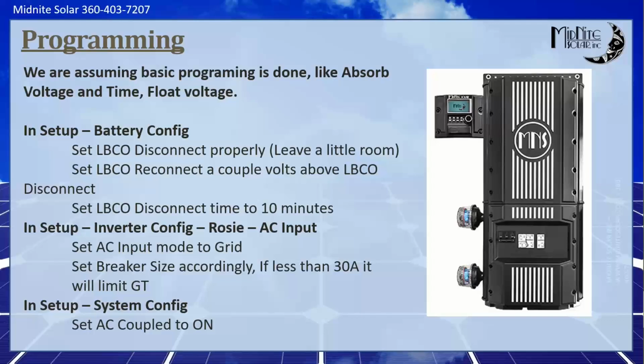But assuming all that's done, really all we have to do to actually make AC coupled work is, as I mentioned, set up our low battery cutout properly to leave a little room, maybe make it trip off at like 25% instead of 0%. And then set your reconnect a couple volts above low battery cutout. This one's important. I worked one the other day where the customer thought the Rosie was defective because it was shutting off 2 or 3 times in the night, but it would come right back on in about 10 seconds.